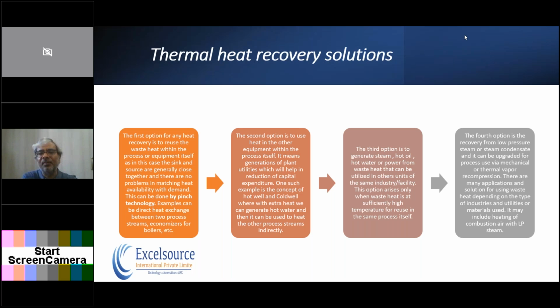And the last option that we come up with is to optimize whatever steam we have used in the plant. Once the heat is utilized from the steam, we generate a low pressure condensate. That condensate also has the possibility of generating flash steam. So we can use the flash steam out of the low pressure condensate, and the condensate with only the sensible heat available can be sent back to the boiler feed water, maybe directly to the deaerator. That is the last option, which we can try to optimize by implementing flash steam generation in the plant. I will give you some case studies that we have done in the industry.